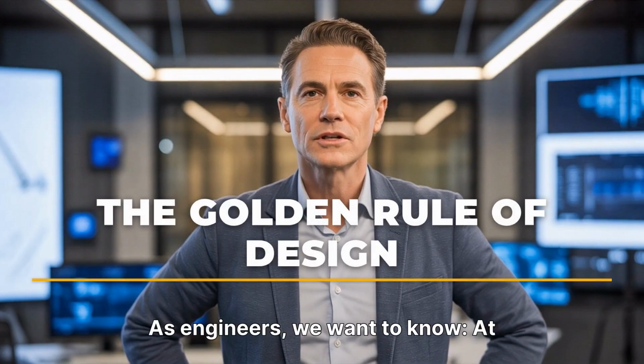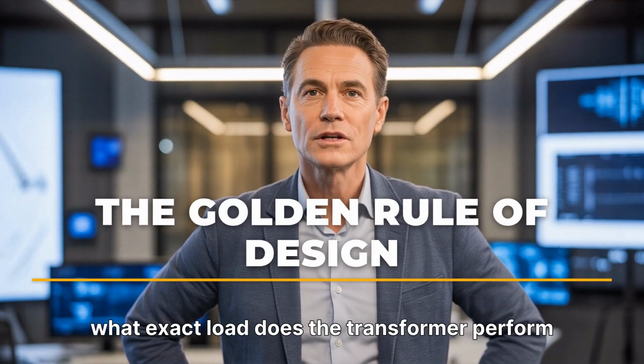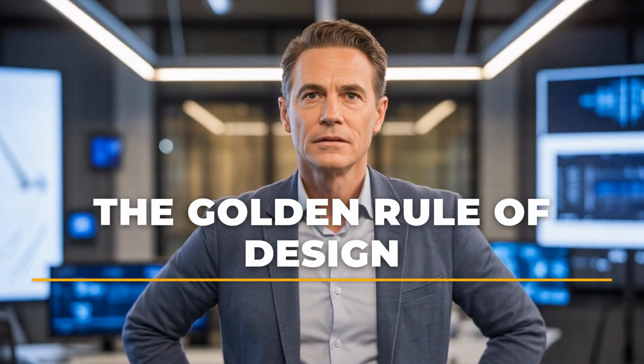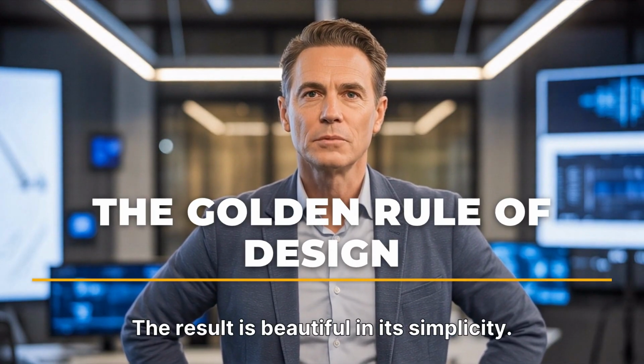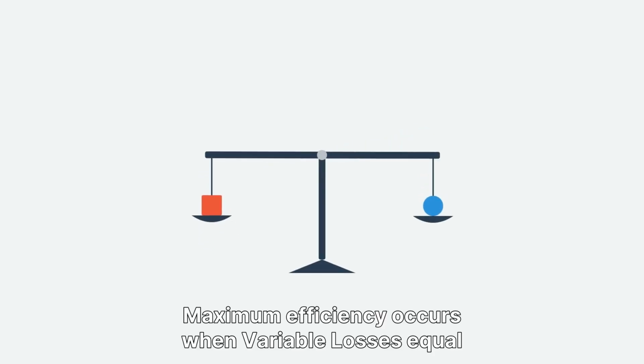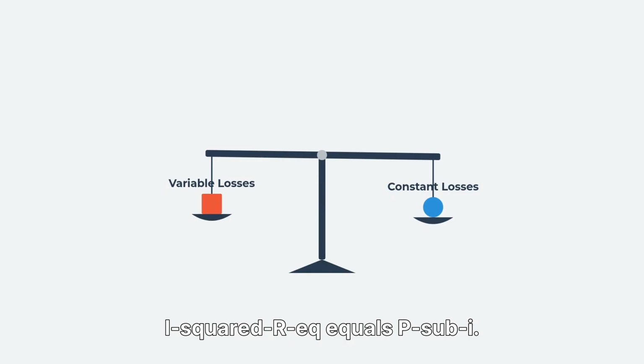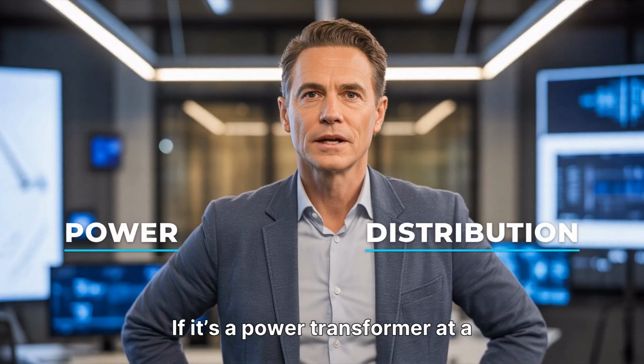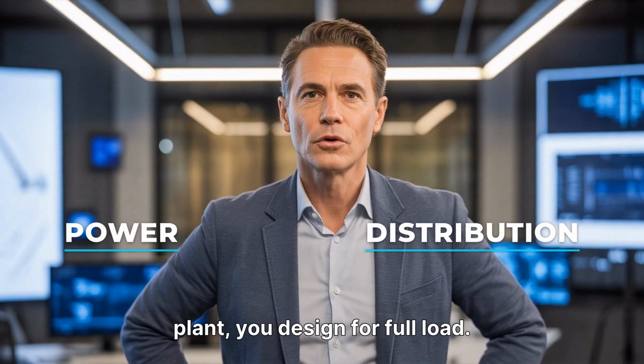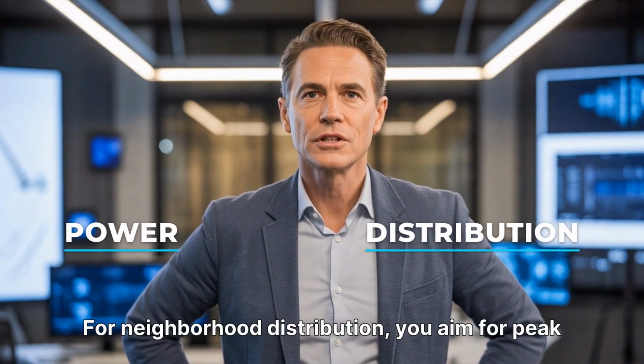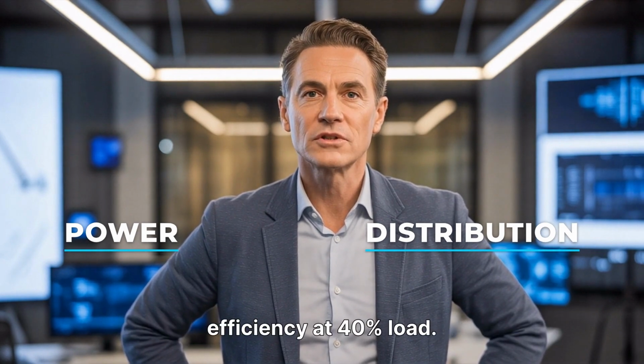As engineers, we want to know, at what exact load does the transformer perform best? The result is beautiful in its simplicity. Maximum efficiency occurs when variable losses equal constant losses. I² R_eq equals P_i. If it's a power transformer at a plant, you design for full load. For neighborhood distribution, you aim for peak efficiency at 40% load.